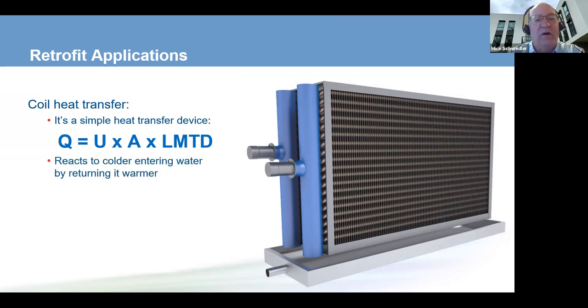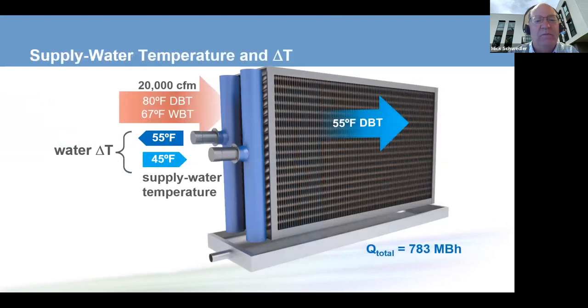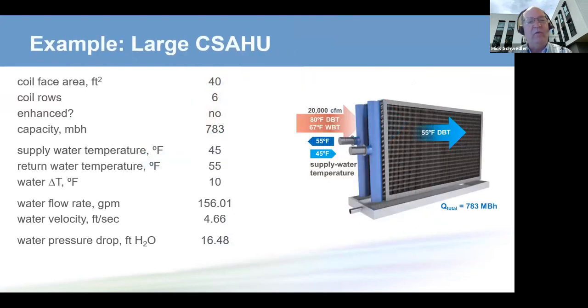If we get colder water, it will use less of the water, and it will come back warmer. So let's take an air handler that's already been selected, already out in the field, selected at 45 to 55 degrees. It is a 20,000 CFM, and we get the 783 MBH for the coil. Now, the goal in this case is to do a retrofit, supply that coil with colder water, and use less of that water.